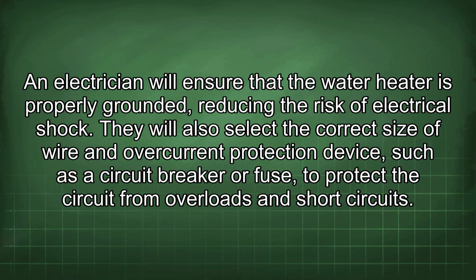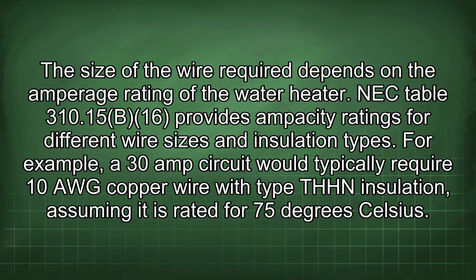They will also select the correct size of wire and overcurrent protection device, such as a circuit breaker or fuse, to protect the circuit from overloads and short circuits. The size of the wire required depends on the amperage rating of the water heater. NEC Table 310.15(B)(16) provides ampacity ratings for different wire sizes and insulation types. For example, a 30 amp circuit would typically require 10 AWG copper wire with type THHN insulation, assuming it is rated for 75 degrees Celsius.